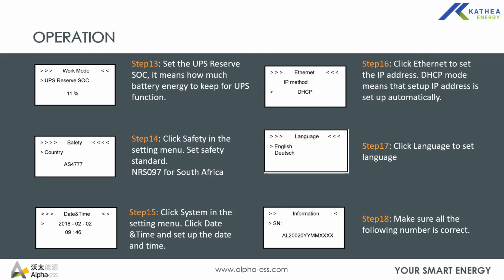But with this setting, please note that when you enable discharge and set time zones, the inverter will only discharge the battery during that period. Regardless of whether it loses grid, that is, when you have load shedding outside of those time zones, the inverter would not discharge the battery because it's set to discharge the battery only at those specific times.